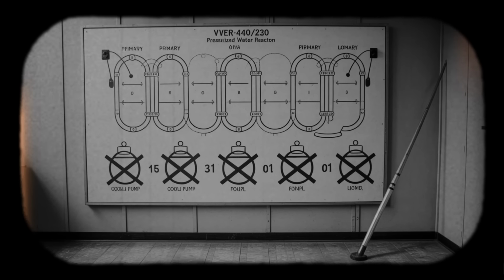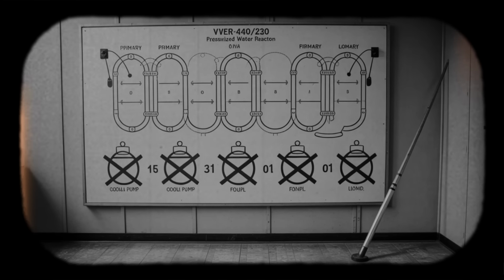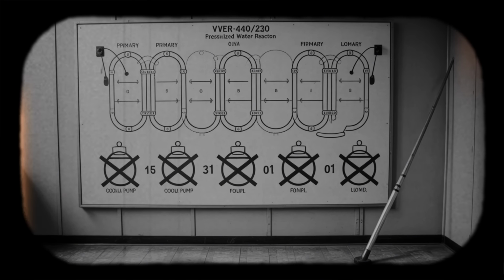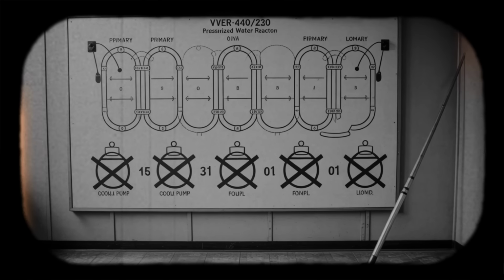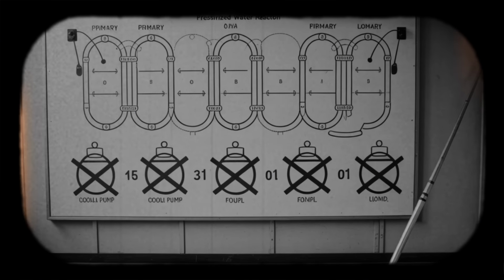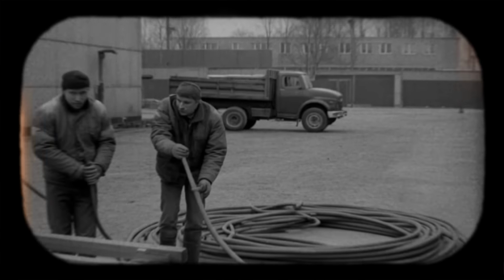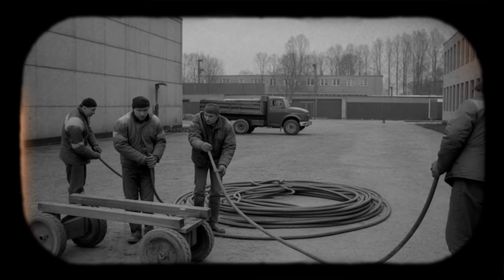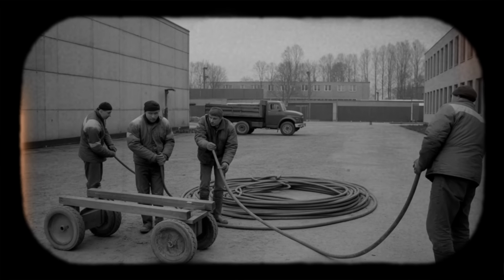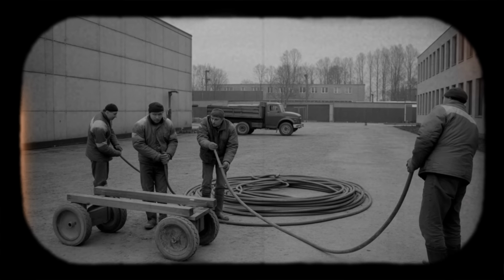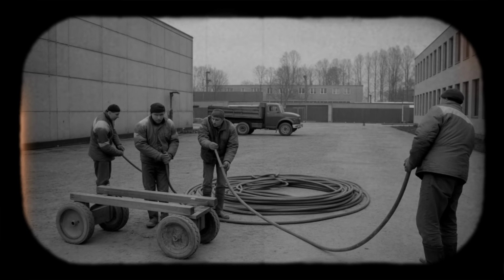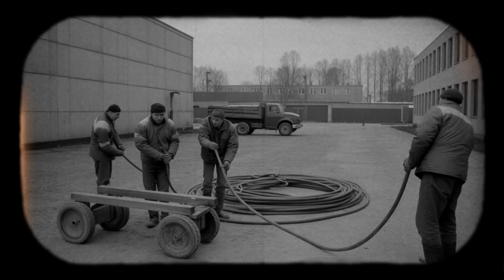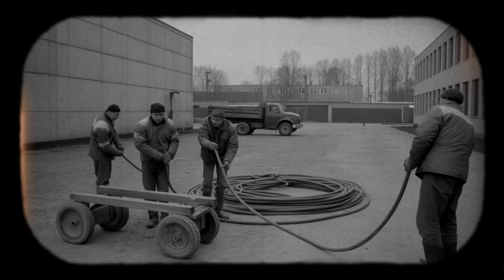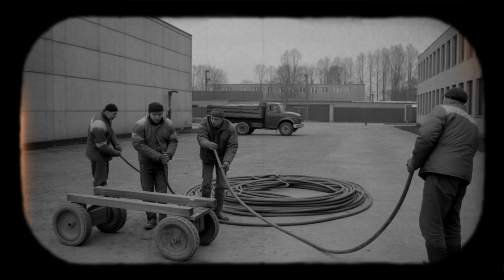Throughout the event, operators worked with incomplete information. The cable fires had cut not just power but also signals. Instrumentation channels that should have provided direct readings of core parameters were degraded, unreliable, or completely failed. Expected situation: after any single fire, at least one full train of instrumentation and control remains available, allowing operators to monitor core parameters directly and make informed decisions about safety system actuation.